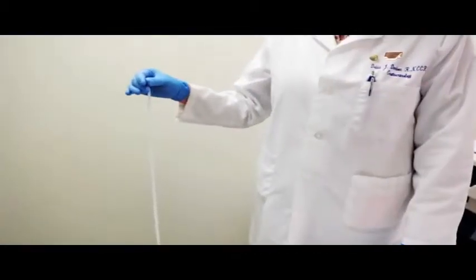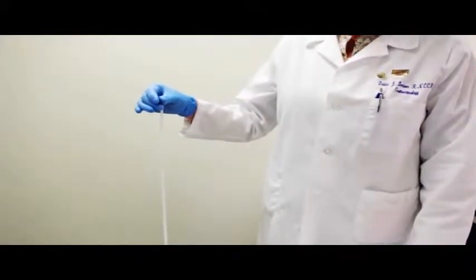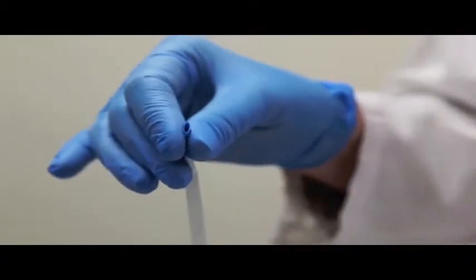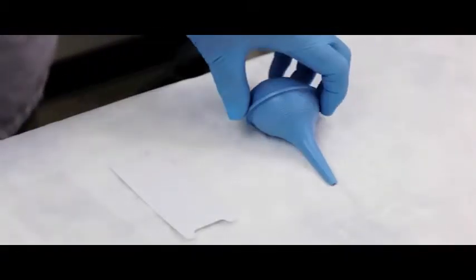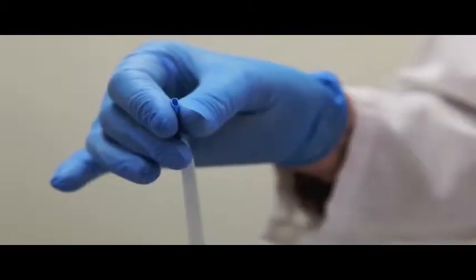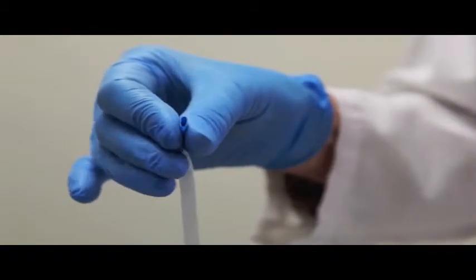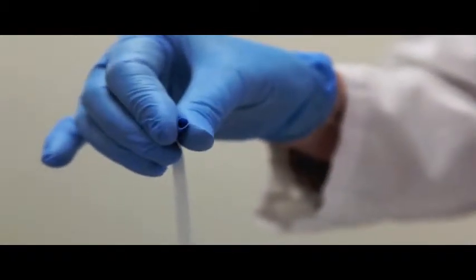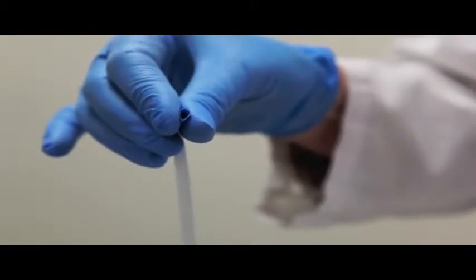Manoshield Integrity Test. Pick up a Manoshield and let it hang down toward the ground. Do not let it touch the ground. Hold the Manoshield at the blue cuff with one hand and pick up the supplied syringe bulb with the other. Gently squeeze the blue cuff open if it is pressed flat. This makes it easier to fit the bulb and insert the catheter.